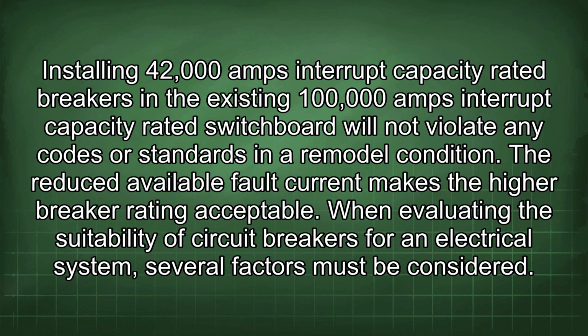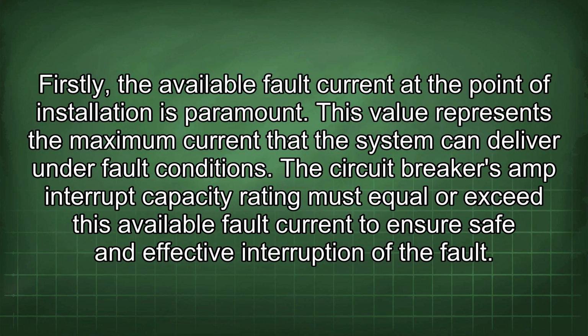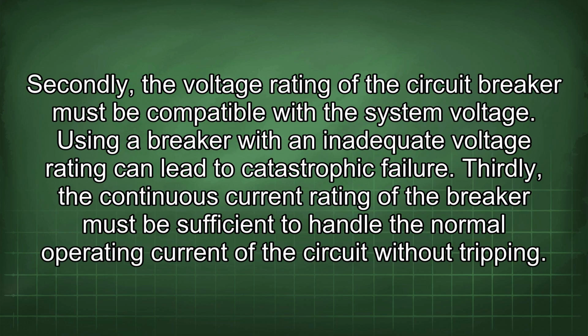Installing 42,000 amps interrupt capacity rated breakers in the existing 100,000 amps interrupt capacity rated switchboard will not violate any codes or standards in a remodel condition. The reduced available fault current makes the higher breaker rating acceptable. When evaluating the suitability of circuit breakers for an electrical system, several factors must be considered. Firstly, the available fault current at the point of installation is paramount. This value represents the maximum current that the system can deliver under fault conditions. The circuit breaker's amp interrupt capacity rating must equal or exceed this available fault current to ensure safe and effective interruption of the fault. Secondly, the voltage rating of the circuit breaker must be compatible with the system voltage.